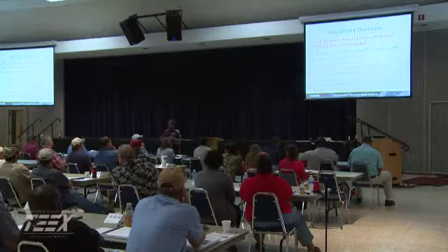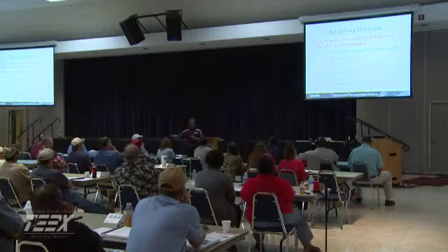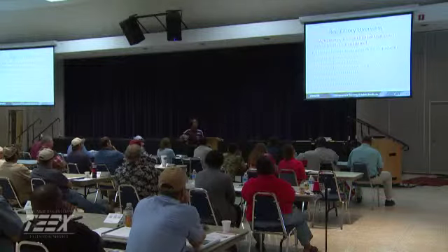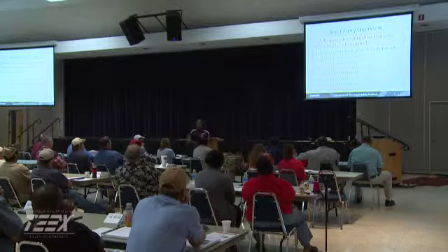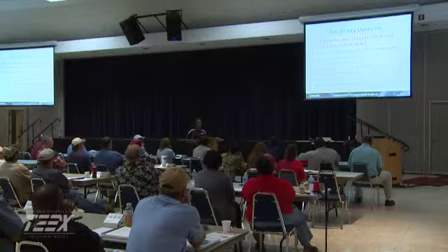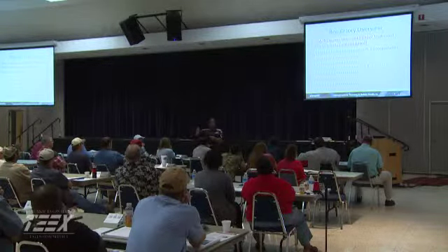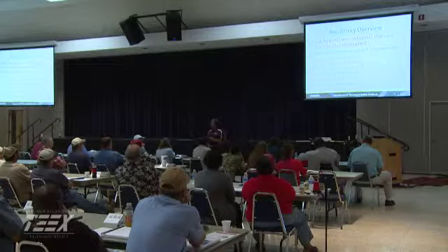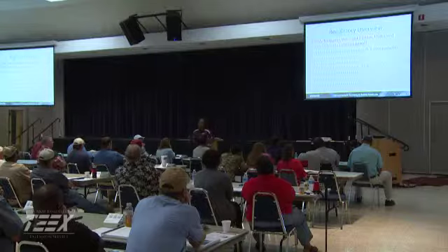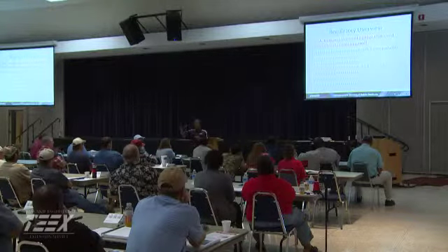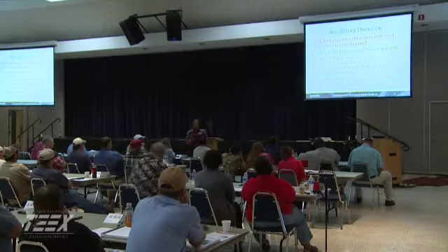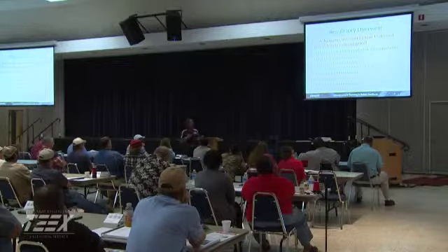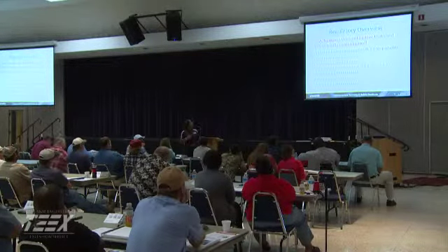Okay, good. What they do is come out and they look at 8 areas, starting with the source water, where you're getting your water from. They look at treatment, distribution. They look at all of your records, compliance, monitoring. So what you have to do in order to get ready for a sanitary survey is make sure you have all your paperwork in a row when they come out. They will do a walkthrough inspection, and then at the end of that survey, they will list deficiencies which they noted, and they will give you time to correct those deficiencies. So that's one component to identifying whether or not you have issues.